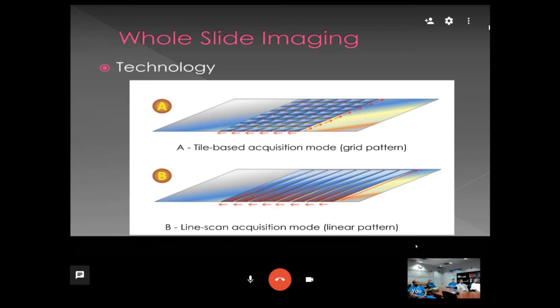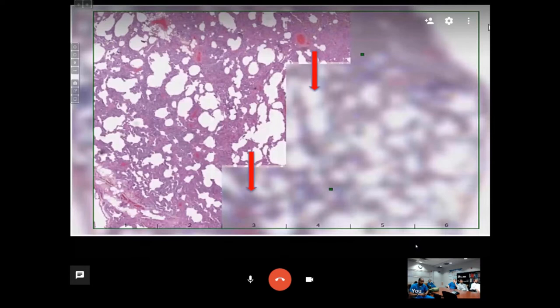Now, most of the scanners today will use a line scan. However, some still use the tile-based acquisition method, but the line scan will scan the entire slide in the short axis and then just continually go to the next direction. This is an example of what one of the slides looked like while it's scanning. You can see the strips that are there, and it scans it in a line-based manner.